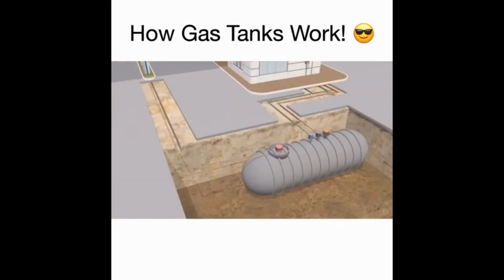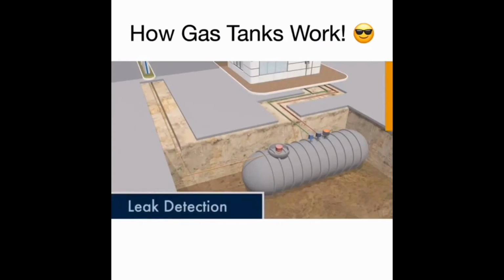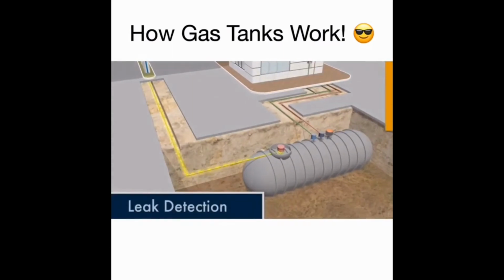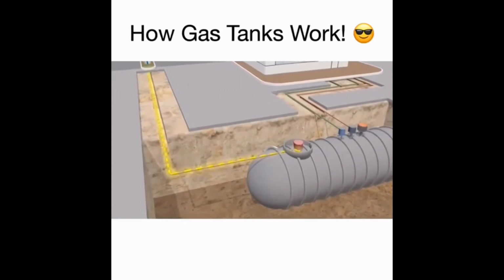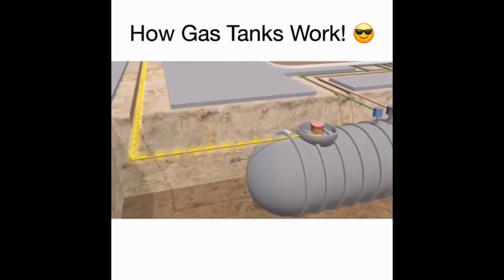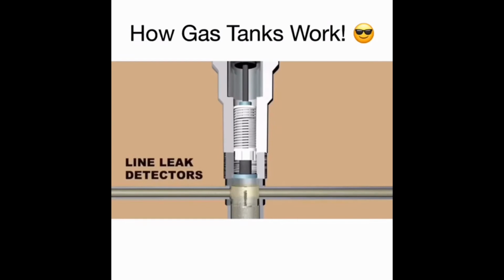But a commitment to safety also means expecting the unexpected. So leak detection is another important feature of underground storage tanks. Sensors can detect even a small leak by comparing the amount of fuel dispensed at the pump with the amount that should remain in the tank. In the pipes leading from the tank to the pump, line leak detectors use a spring-loaded probe to test fuel pressure. An unexpected change in pressure will trigger an alarm.